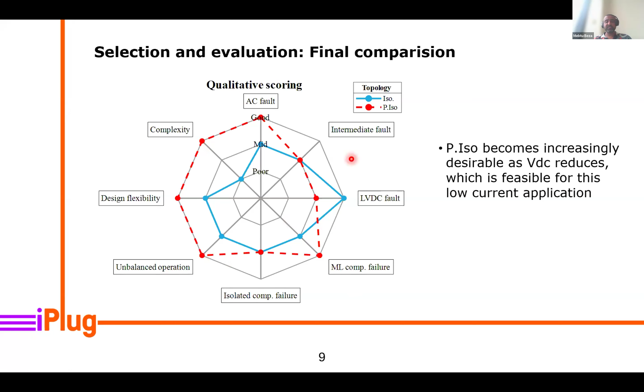So the recommended topology uses full bridge cells in a back-to-back setup, choosing a voltage level lower than half of what would be used in a half bridge setup, and using dual active bridges as an isolated stage to go from intermediate DC to low voltage DC. To realize this, we use a series connection on the input side and a parallel connection on the output side. This is the topology we go for.